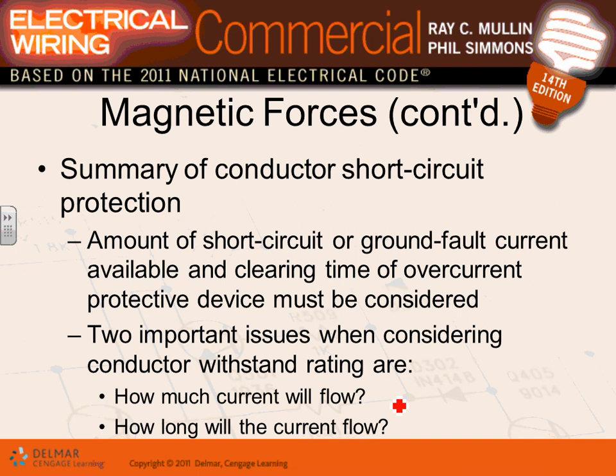Okay, magnetic force, summary of conductor short circuit. So clearing time, the amount of short circuit or ground fault available, and the clearing time of the equipment. So all these tell you how much short circuit or ground fault is there, and what's the clearing time of the equipment. How much current and for how long? How much current for how long?